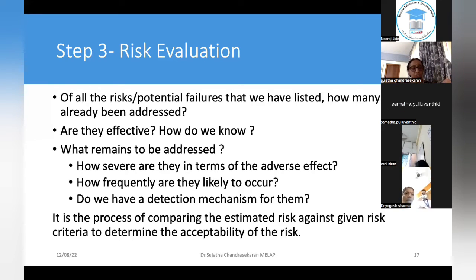If it is a bacteriology or a molecular test, or the equipment, if the lamp is failing, not fully failing, or if the aspiration isn't good, if there are air bubbles. These are all the risks that happen during a test that is done even in automated equipment. So imagine the manual things. Manual things have more risks. So these you have already addressed by running an IQC.